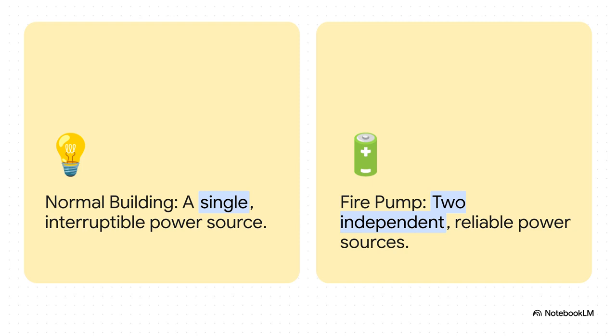You know, think about the lights in your office, your computer. They're all running off the building's main power. If the power goes out, everything goes dark. Simple as that. But a fire pump? No way, it can't take that risk. So the code demands it has at least two totally independent and reliable sources of power.